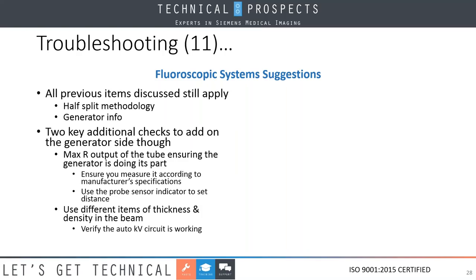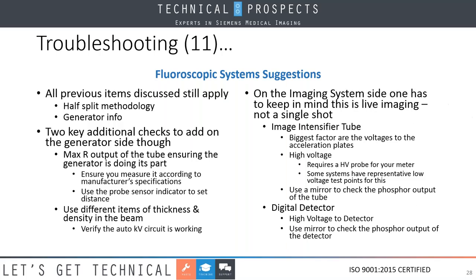Couple of key things to check on the generator, though. All right. Are we getting max R output? Because we are limiting the radiation to a max R in fluoro. Are we getting it? All right. That's going to determine, you know, how good the quality of our fluoro exam is. All right. The auto KV circuit, is it working? So as you're testing this, you put something in the beam of a different density from where you're starting out. All right. Make sure that works.